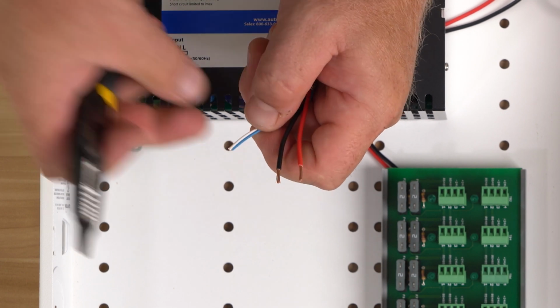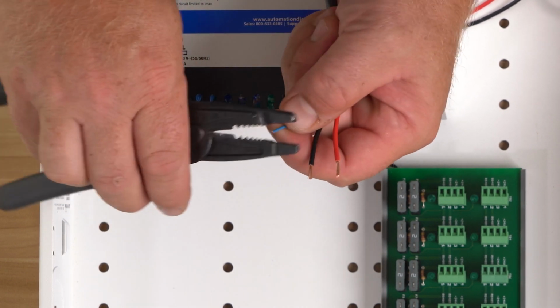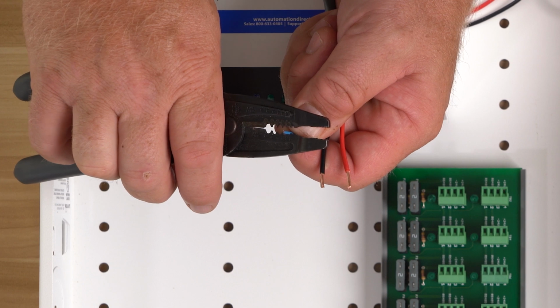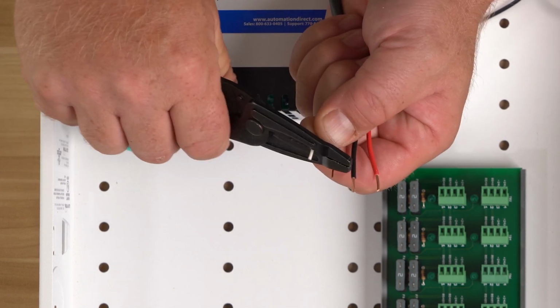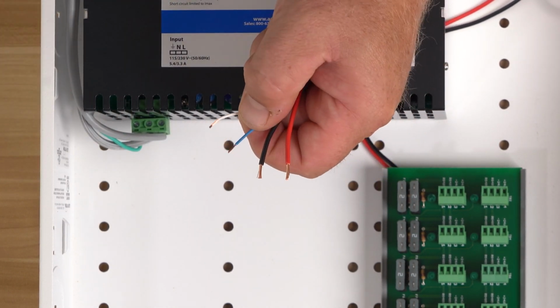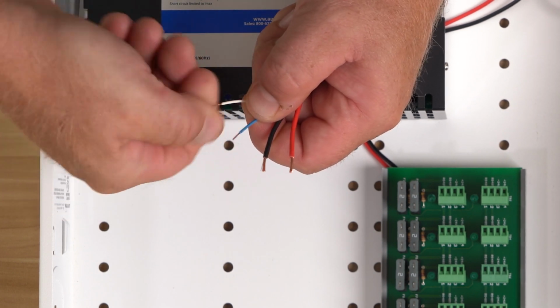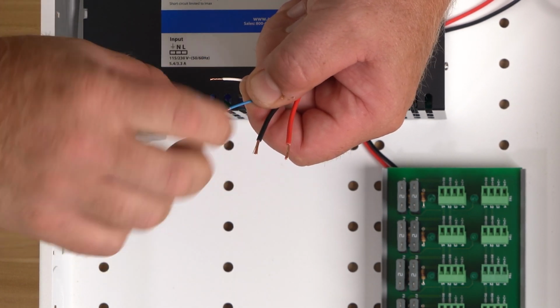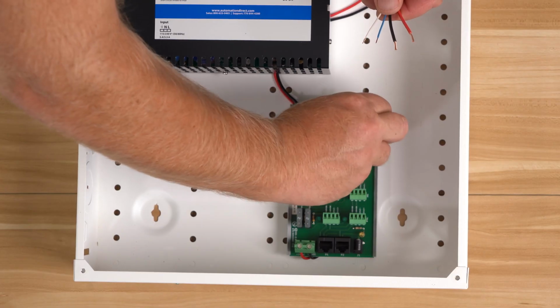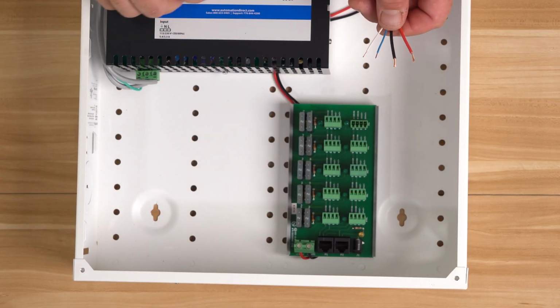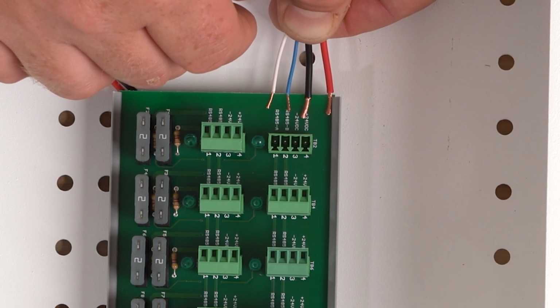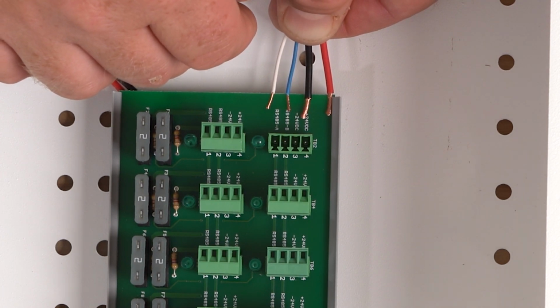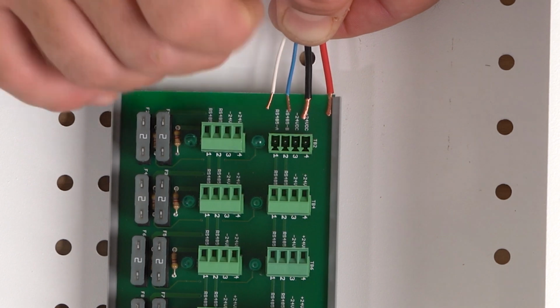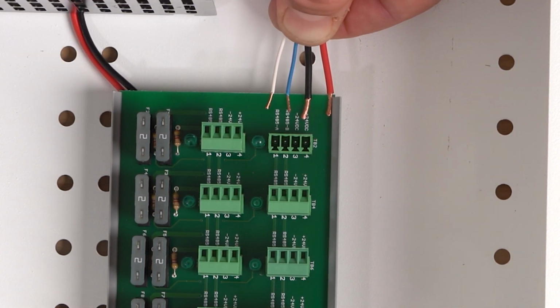And then for the two data wires, these are 24 gauge, and you can strip them at 24 gauge. Go ahead and give everything a nice quick little twist so that they all stay together when you put them inside the Phoenix connector. Take the Phoenix connector out. And the way that we set this up was positive and negative. Positive's red, negative's black. RS-485 A and B. Well, we figured B, blue, and then A can be whatever's left over. It's typically a white or a yellow wire.